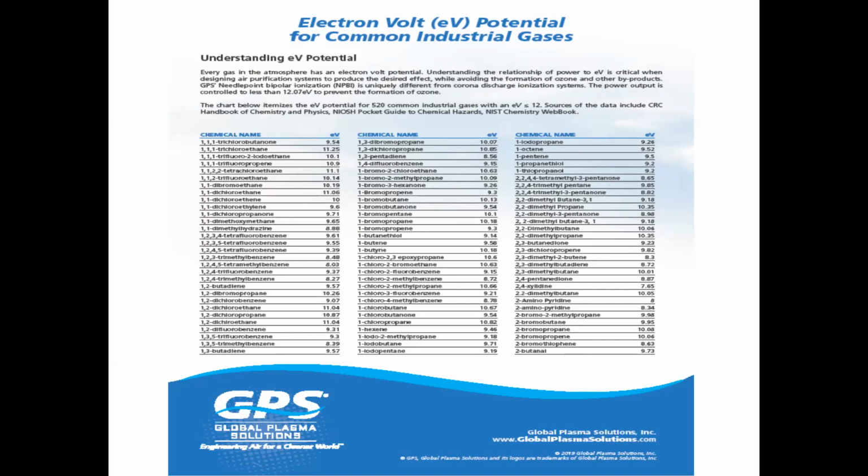Normally, when they agglomerate, your filter will pick them up. Some will get heavy enough that they'll drop out of the airstream, but most of them, in fact, if you measure particulates before and then a couple of days after we install, you'll actually see more particulates a couple of days after, because those ultrafine particulates that most particulate counters can't pick up are getting bigger, and you'll see larger 2.5 volumes for the first couple of days. Then if you test it in 5 or 6 days, you'll see a dramatic drop.